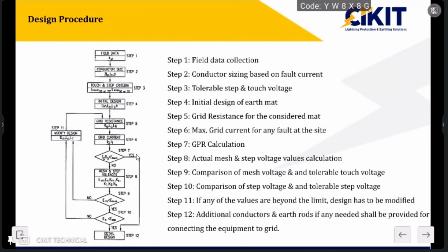IEEE 80 has provided a detailed description of the design procedure for the earth mat. The first step is field data collection, where we collect the details from the field. Second is conductor sizing. Third is step and touch voltage calculation. Fourth is initial design of the earth mat. Fifth is grid resistance. Sixth is grid current calculation. Seventh is GPR calculation. Then we calculate the actual step and touch voltages. Then we compare the mesh voltage with the tolerable touch voltage, and the step voltage with the tolerable step voltage, and we make modifications if they are not within the limit.